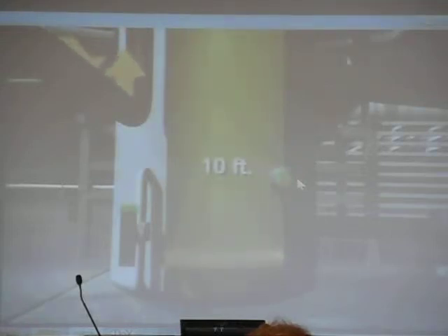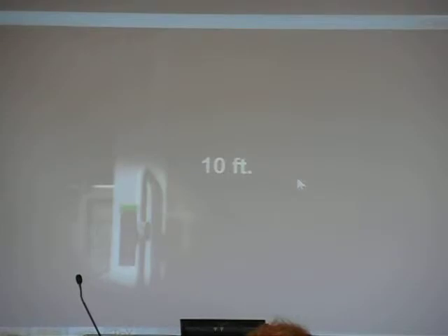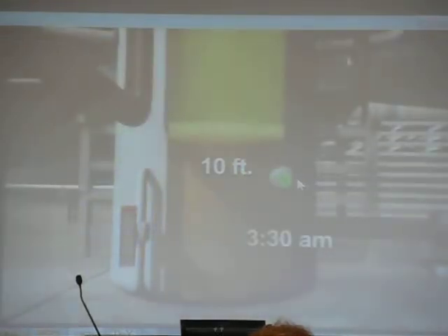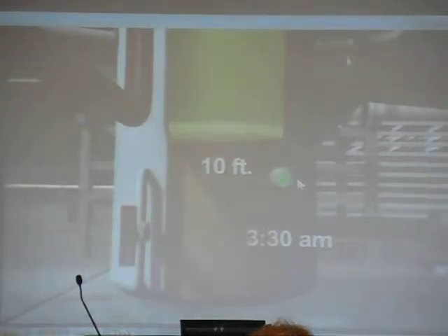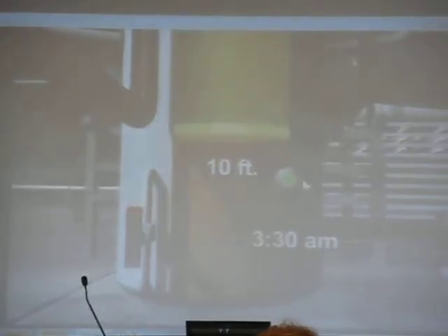This indicator was not designed to measure any liquid above the 10-foot mark. Above that point, operators would have no idea how high or how dangerous the level was. A high-level alarm activated and sounded in the control room with the tower overfilled, but a second, redundant alarm failed to activate. By 3:30 a.m., the feed was stopped, and the level indicator showed that the liquid had filled the bottom 10 feet of the tower. We now know that this indicator was not providing accurate readings.